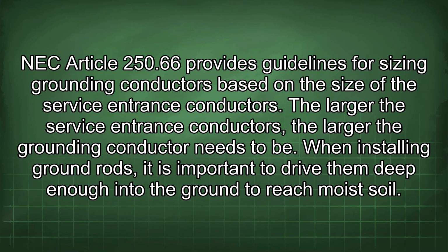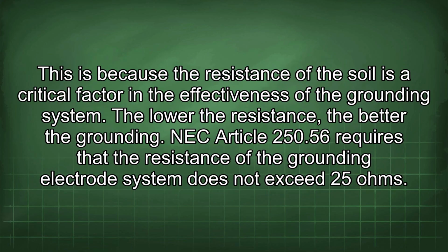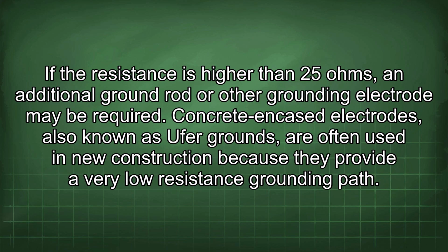When installing ground rods, it is important to drive them deep enough into the ground to reach moist soil. This is because the resistance of the soil is a critical factor in the effectiveness of the grounding system. The lower the resistance, the better the grounding. NEC Article 250.56 requires that the resistance of the grounding electrode system does not exceed 25 ohms. If the resistance is higher than 25 ohms, an additional ground rod or other grounding electrode may be required.